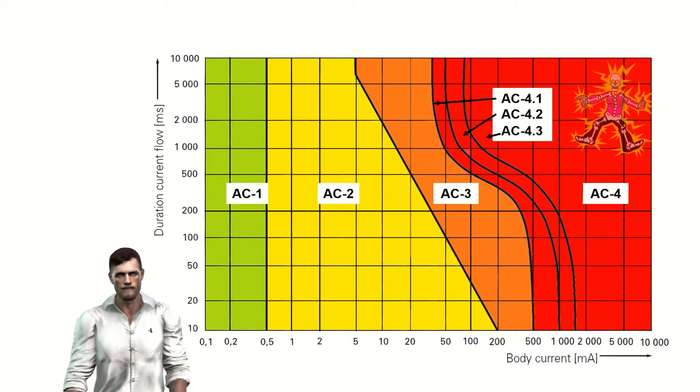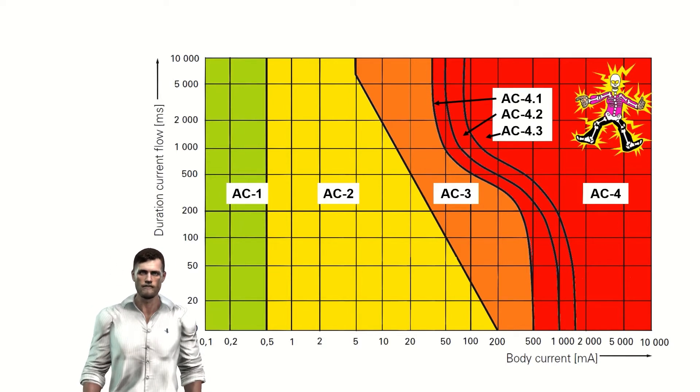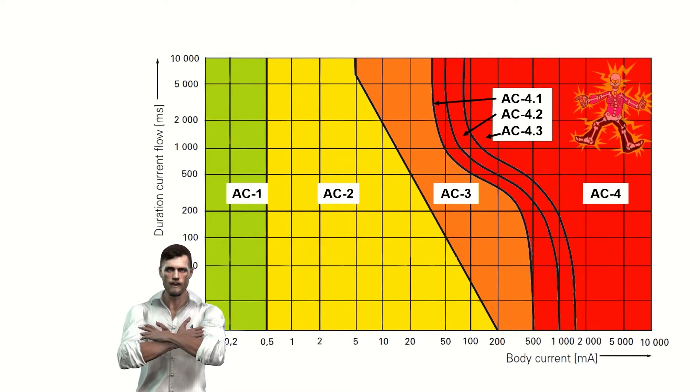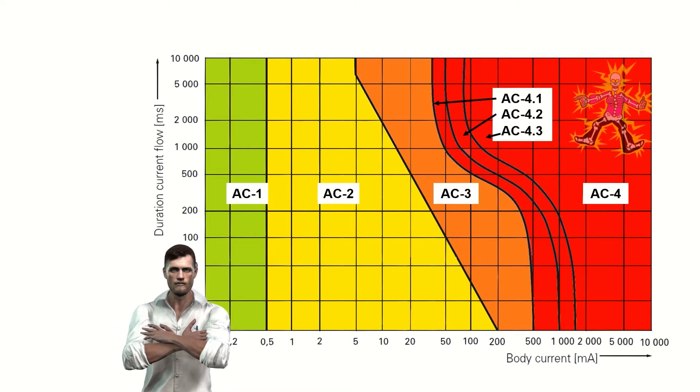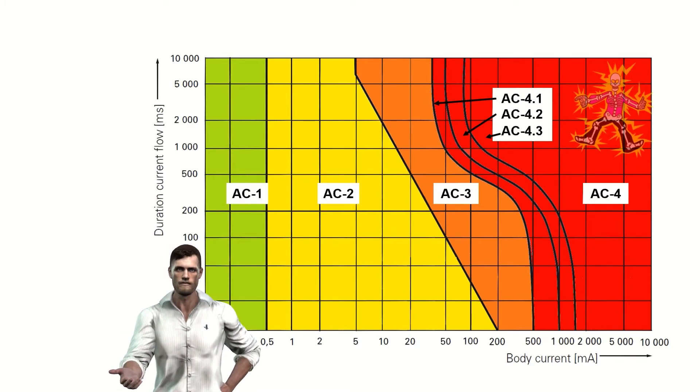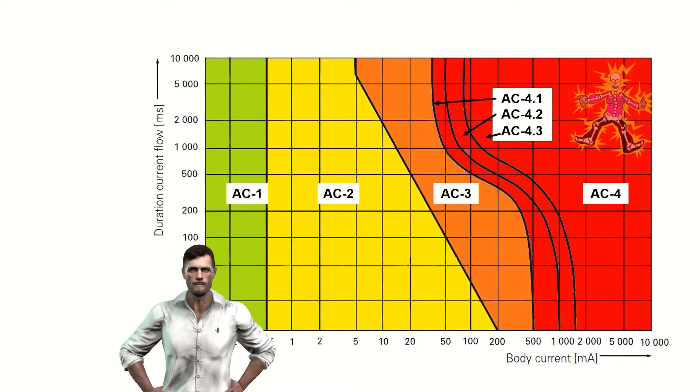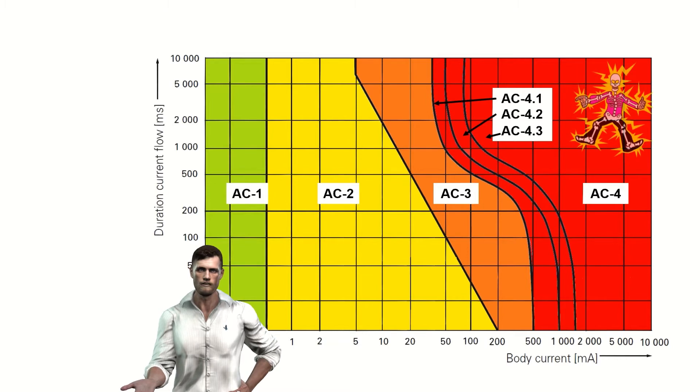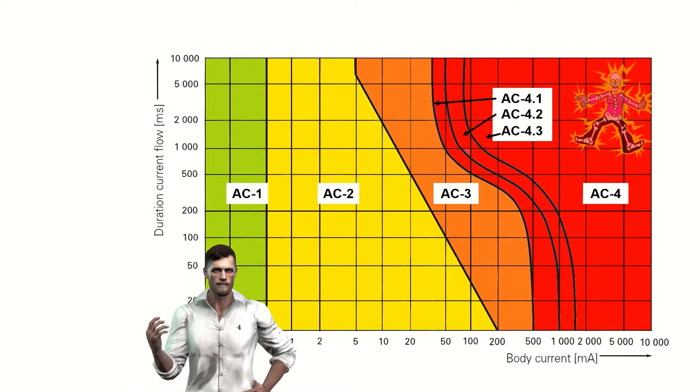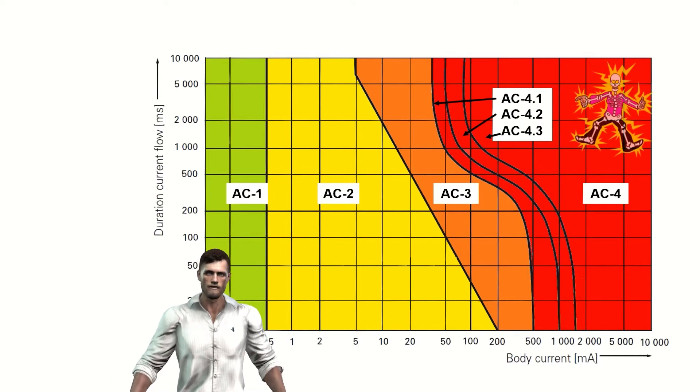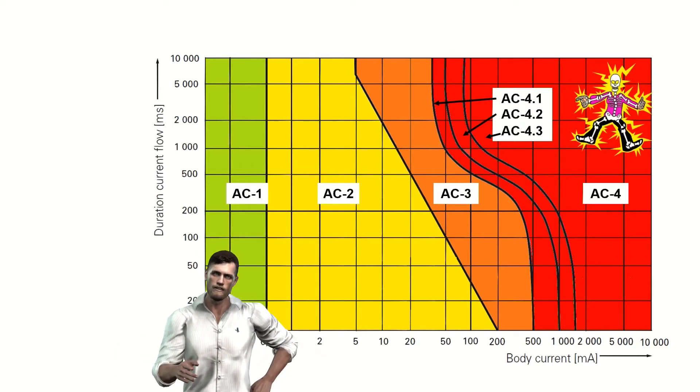In zone AC4, we already have the possibility of suffering irreversible effects. For example, in zone AC41, we would have up to a 5% probability of suffering cardiac fibrillation. In zone AC42, up to 50% and in zone AC43, more than 50%. Therefore, the objective of the differential protection or RCD is to open the circuit before we can enter the most dangerous zone, that is the AC4 zone, where as we have mentioned, the effects can already be irreversible.